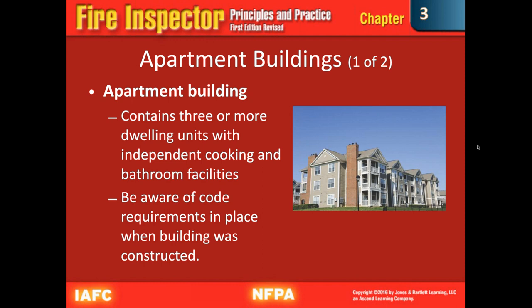All right, so when it comes to these, you must be aware of the code requirements in place when the building was constructed, and sometimes they may differ from those for newer buildings. Especially if they haven't been renovated more than 50%, they don't have to bring everything up to code. So if it's an old building with a new addition that is not over 50%, it's going to make your life a little harder because you're going to have to keep up with the old code that things got grandfathered in, as well as the new code for the renovations.